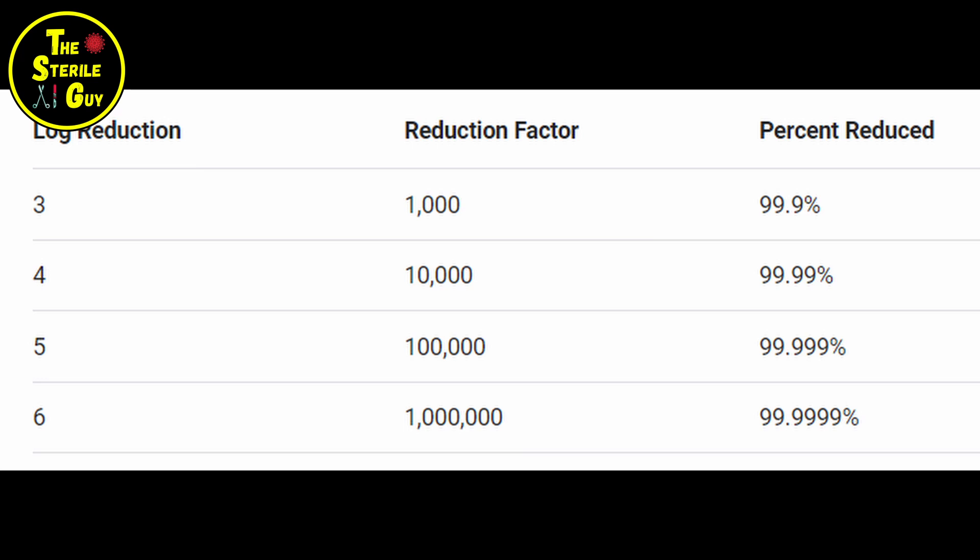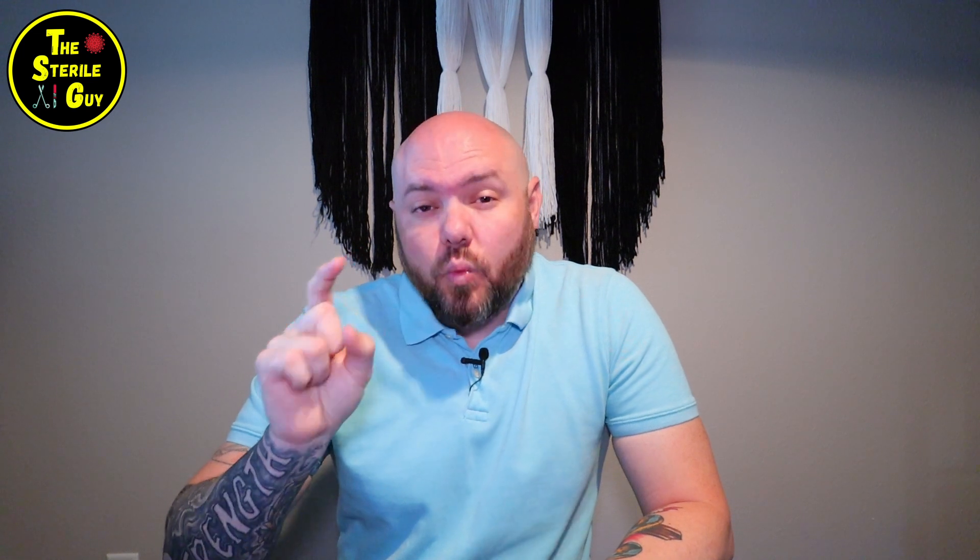If you look at this chart, you can see that each increase in a log reduction moves the decimal point over — a three log is a one in a thousand chance, five log is a one in a hundred thousand chance. Since we are tasked by the FDA with achieving a six log reduction, this is why biologicals contain a colony of at least one million spores. If all one million microorganisms from that vial are completely destroyed through the sterilization cycle, you have met the six log reduction.